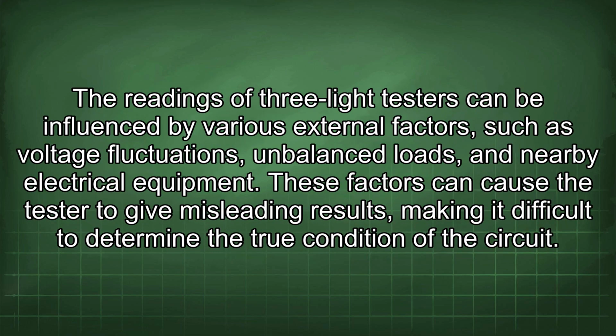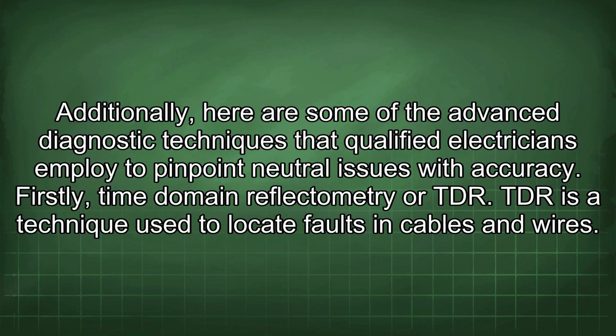The readings of 3-light testers can be influenced by various external factors, such as voltage fluctuations, unbalanced loads, and nearby electrical equipment. These factors can cause the tester to give misleading results, making it difficult to determine the true condition of the circuit. Additionally, here are some of the advanced diagnostic techniques that qualified electricians employ to pinpoint neutral issues with accuracy. Firstly, time domain reflectometry, or TDR.